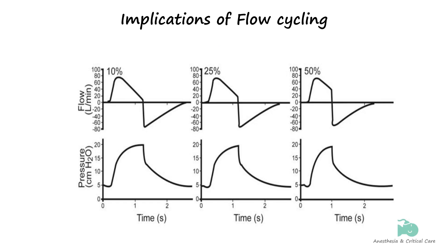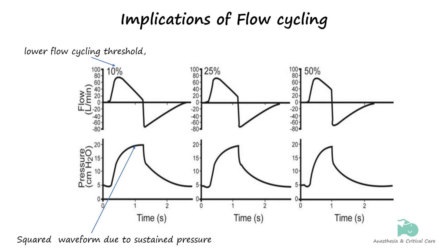Also, with a lower flow cycling threshold, the inspiratory pressure remains elevated for a more extended period as the flow takes longer to reach the threshold for cycling from the peak value. This results in a more sustained square waveform. Conversely, with a higher flow cycling setting, the inspiratory pressure declines more rapidly as it is easier for the flow to reach the higher cycling threshold, so less squaring is seen with higher cycling values.